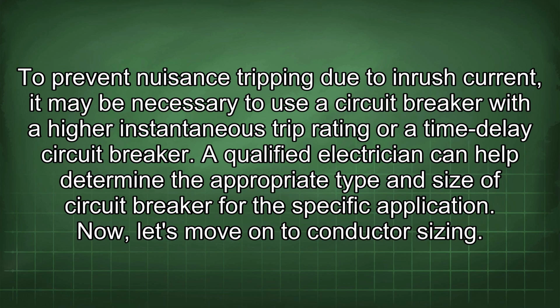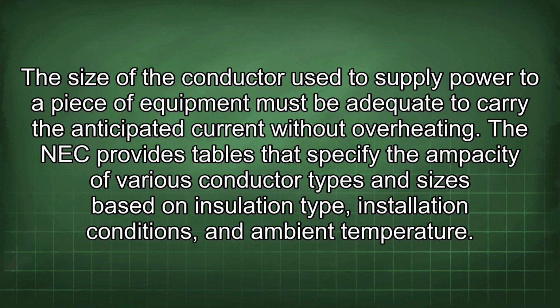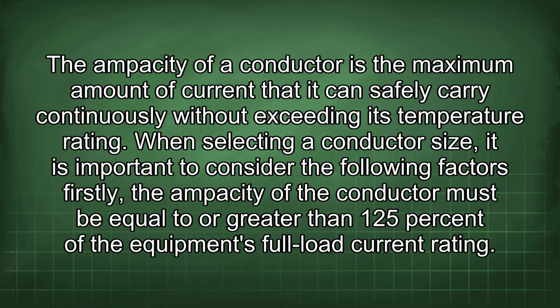Now let's move on to conductor sizing. The size of the conductor used to supply power to a piece of equipment must be adequate to carry the anticipated current without overheating. The NEC provides tables that specify the ampacity of various conductor types and sizes based on insulation type, installation conditions, and ambient temperature. The ampacity of a conductor is the maximum amount of current that it can safely carry continuously without exceeding its temperature rating. When selecting a conductor size, it is important to consider the following factors.